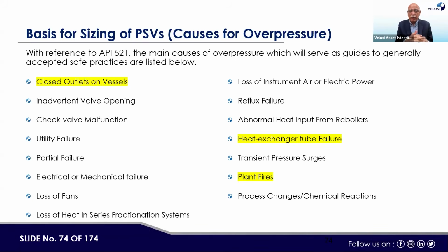However, the reciprocating or positive displacement machines, whether pump or compressor, will keep increasing the pressure until the fluid gets some exit point. So if the outlet is blocked in any system, say there's a pump or a compressor, then piping, some equipment, some exchanger, and then a valve, and that valve is closed for some reason, the fluid has to go out somewhere. So you need to put a PSV to provide that path, and that PSV sizing would be done on the assumption of the outlet blocked.